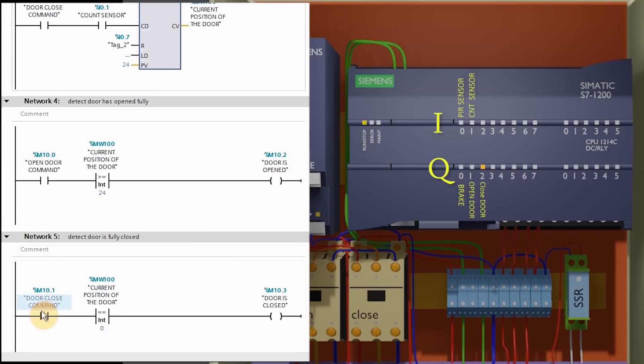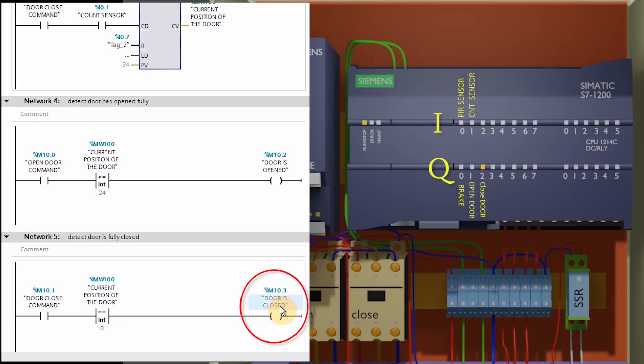Network 5 is used to detect if the door has closed. A comparison instruction compares the current counter value with 0 — if the current value equals 0, this means the door is fully closed and it will turn on memory bit M10.3, which tells us the door has fully closed.